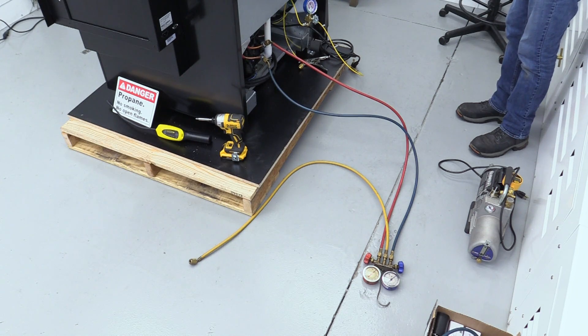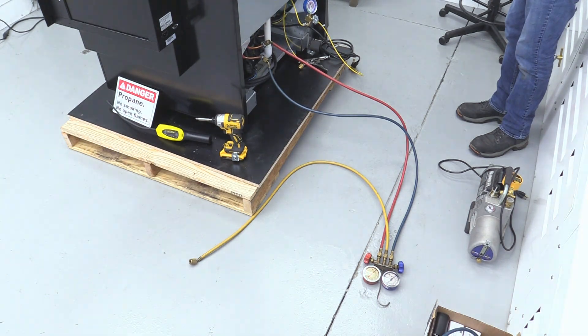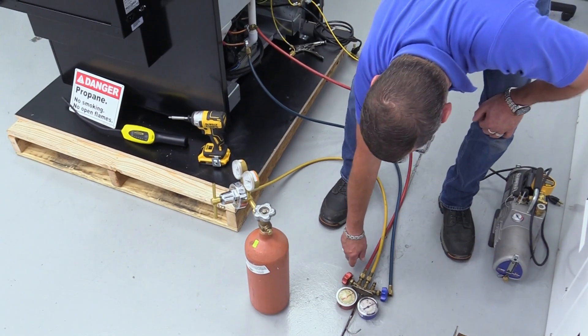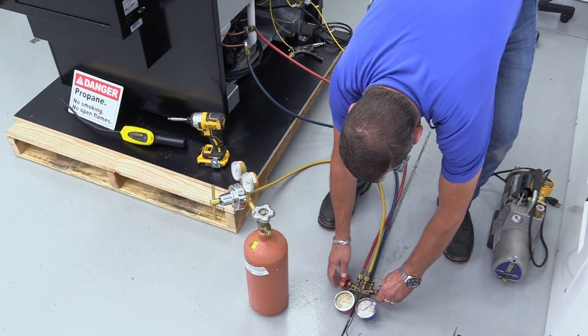If you must recover refrigerant, use an R290 approved recovery machine. Flush the system with nitrogen at 30 to 50 PSIG for a few minutes.